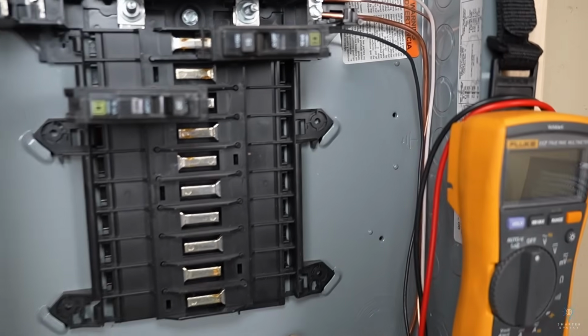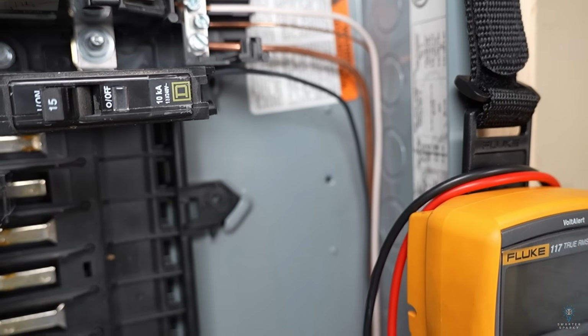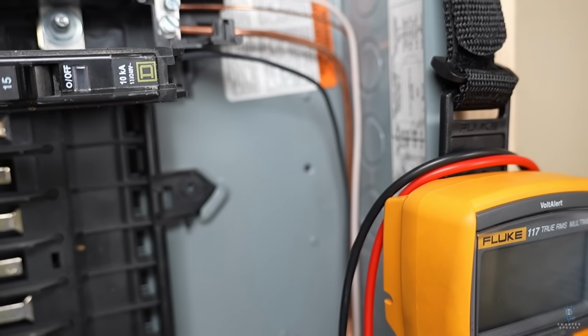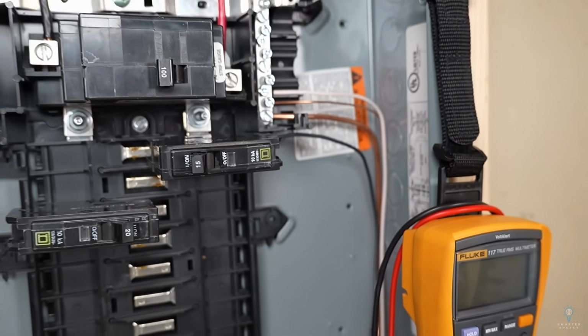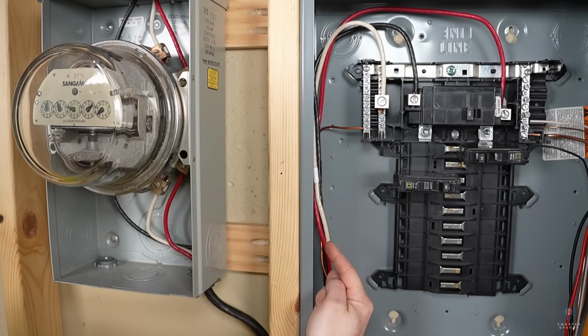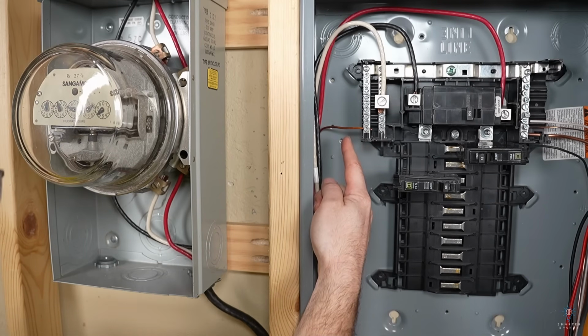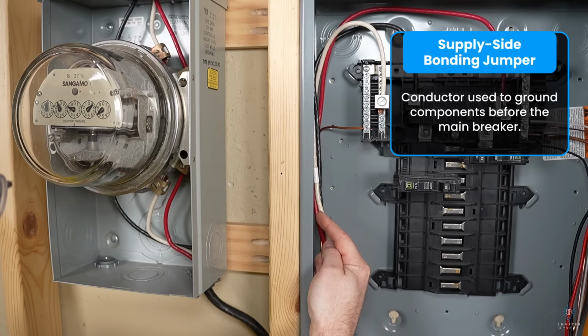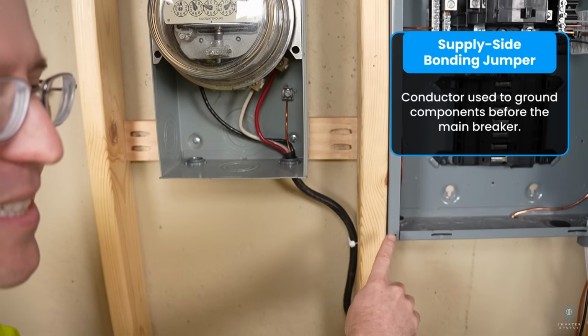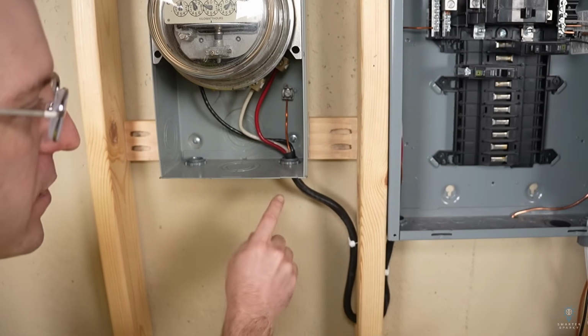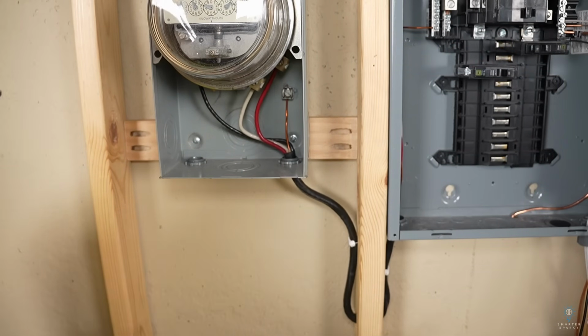They have nothing to do with tripping a breaker. The only time they carry current is during a lightning strike or a large surge. Earlier we saw a ground wire entering with the service conductors. This is actually called a supply side bonding jumper. And that bonding jumper extends the ground connection back to the meter socket or emergency disconnect.